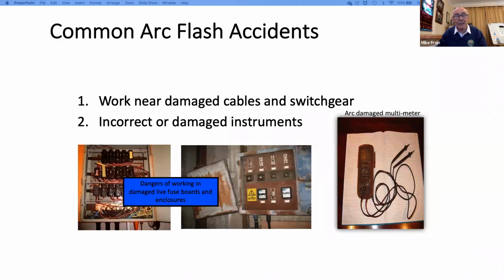And finally, just in terms of my examples, this last one is a common denominator in so many arc flash incidents. It's working on damaged or defective equipment using incorrect or damaged instruments. And you can see there the two fairly badly damaged distribution boards, weathered and so on. They were still live when I took those pictures. On the right hand side, that's an instrument which was involved in an arc flash incident.